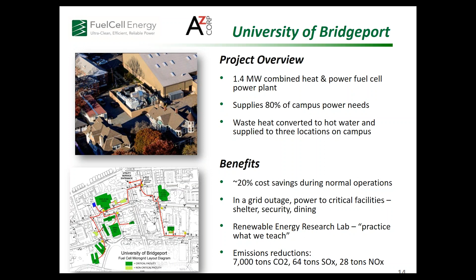The University of Bridgeport project was a recipient of a grant from DEEP, which will allow the university to automate the on-site medium voltage 13.8 kV distribution loop. On campus there are approximately nine G&W switches, all of which are being removed and replaced with motor-operated switches. We're installing an SEL microgrid controller, which will allow the campus to automatically open and close loads and manage the load to the output of the fuel cell if they are in an island mode.